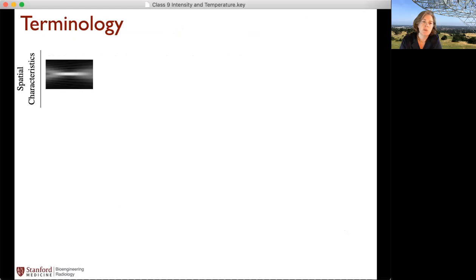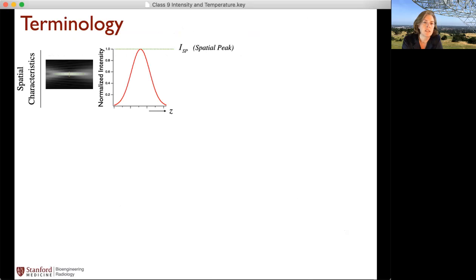All right, so I want to talk a little bit about the terminology for our beam patterns. First of all, there's spatial characteristics. So this is our focus right here. If you take a line drawing, you could draw it either way. It just affects the width of the intensity. So this is a line drawing as a function of space. And of course, you can define the intensity that is the peak. And you can also say, what's the spatial average if you're averaging across that spatial pulse. And so these would be the intensity for spatial peak and spatial average.